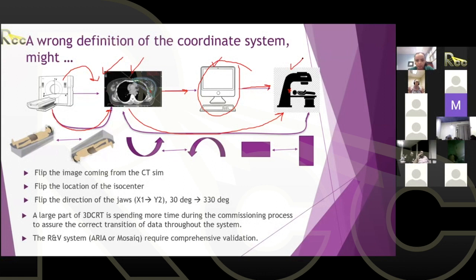Just because they're from the same vendor doesn't mean there will be smooth communication. You have to verify it is smooth, because as I said, they're made to be independent, so that they can communicate with anything - they act as independent units.